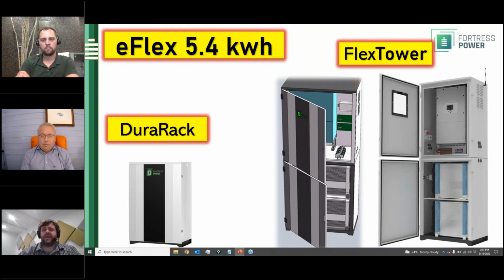We have a brand new cabinet for the eFlex, and it's unique in that you could just buy the lower unit, called the DuraRack, which is a NEMA 3R battery cabinet with an included DIN rail that's particularly useful for adding a heating element or thermostat into the battery box. Lithium batteries can get down to freezing temperatures, but just because you can doesn't mean you should, even though that's the maximum range of the battery.